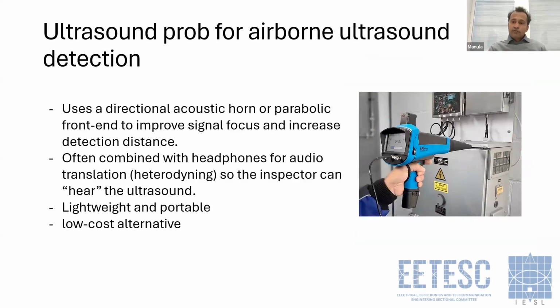The device used to detect airborne ultrasound is called an ultrasound probe, which is normally a microphone. It is nothing other than a microphone. We can have this ultrasound microphone integrated into the device, and scan over the areas or suspected areas to detect if there is an ultrasound source, for example, a partial discharge. So how do we perceive whether there is an ultrasound source or not? As you can see in this picture, there is a sound pressure level measured in decibels. Based on the decibel level, we can guess if there is a strong ultrasound source present or not.